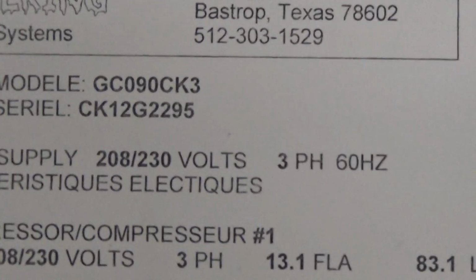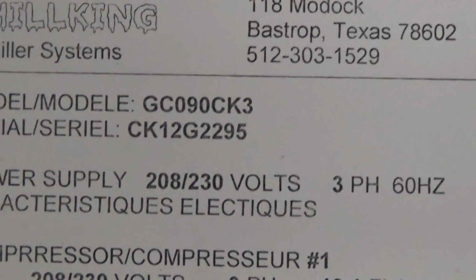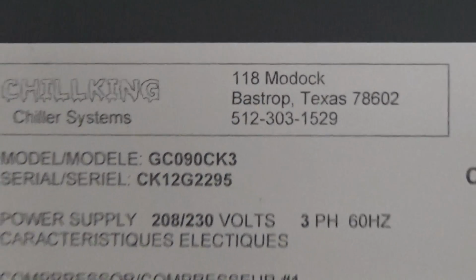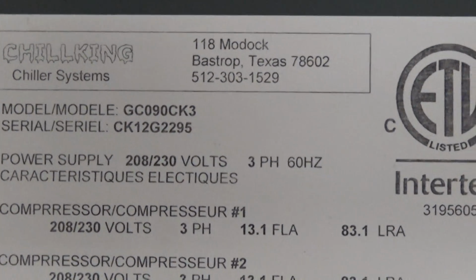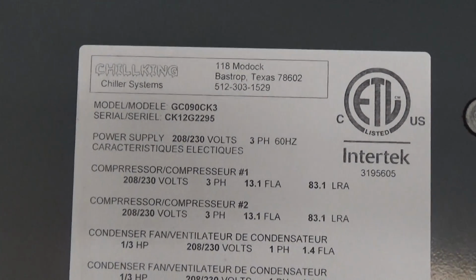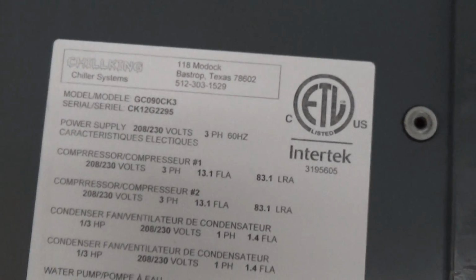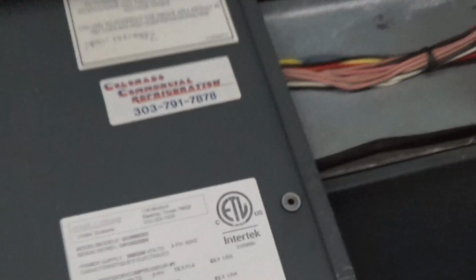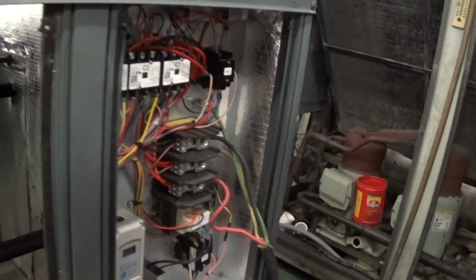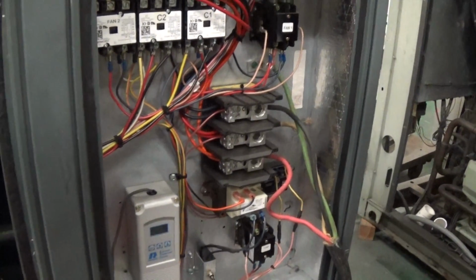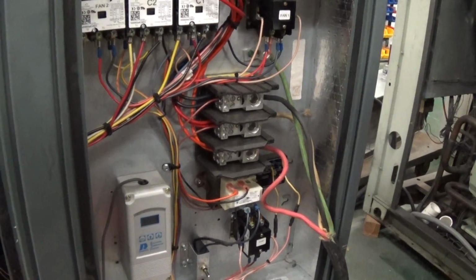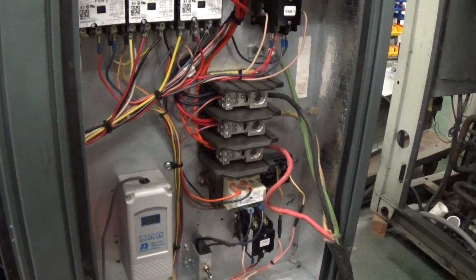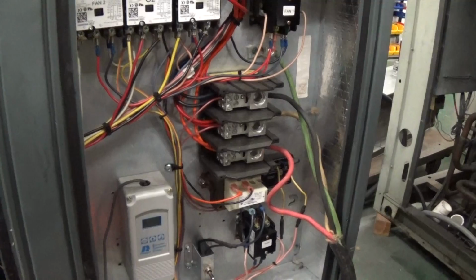This unit, again, is a 2012. It's the model GC090CK3. The 90 stands for 90,000 BTUs at nominal chiller temperatures. We're going to go ahead and just power the unit up, and in this one case here, we're just going to do a few redundant things, just confirming what the electrical requirements of this unit are.